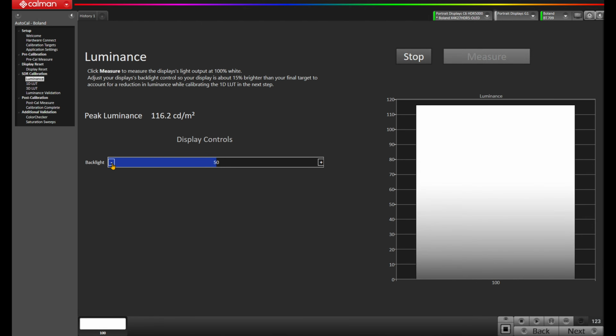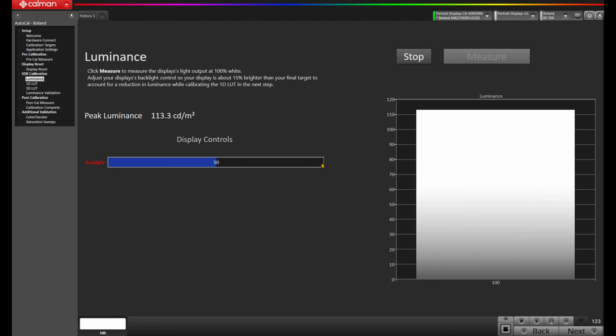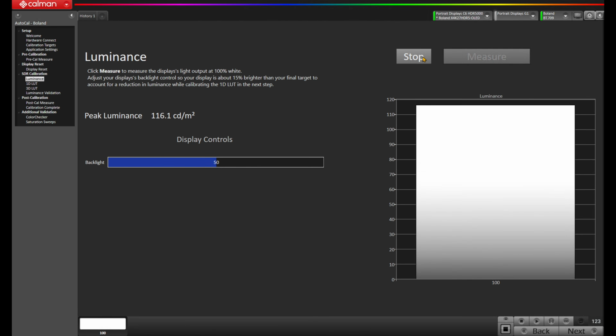But if you wanted to make an adjustment, you can click on these plus or minus arrows and bring it up or down. So as I click it down, you'll notice we come down to 49 and we're at 113.3. So a little lower than 15%. As I come up to 51, you'll notice we're measuring at about 118 candelas per meter squared. So 50 seems to be the right spot for where we want to start. I'll put this back at 50. I'm going to press stop on the reading here in the top right, and let's press next on the bottom right.